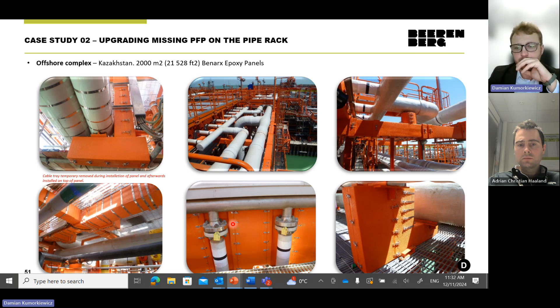Then you have this example with PFP under grating using our panels. Normally when applying PFP it's not allowed to use a heater, so we use this approach instead, with the top flange of the beams left not fireproofed. Our panels are designed for a three-sided scenario and equipped with lugs. We also fireproofed the firewall of the cooling towers, which is why you see these vertical panels.